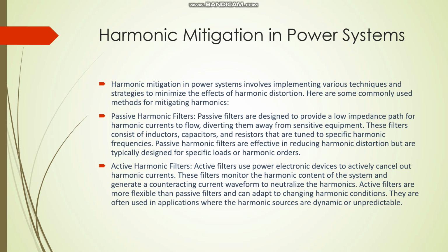Passive harmonic filters. Passive filters are designed to provide a low impedance path for harmonic currents to flow, diverting them away from sensitive equipment. These filters consist of inductors, capacitors, and resistors that are tuned to specific harmonic frequencies.